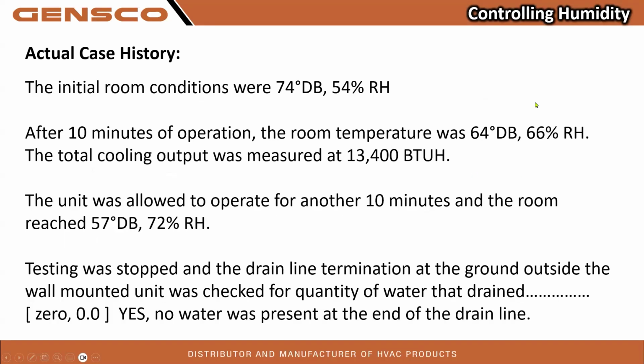The initial conditions were 74 degrees and 54% humidity. And after 10 minutes of operation, that room temperature was down to 64 degrees, 66% humidity. Humidity went up. And the total cooling output, this is not unusual, was double what it's rated to do. Ductless units overproduce. The unit was allowed to operate another 10 minutes and the room reached 57 degrees. That's a 17-degree drop in dry bulb temperature, and my humidity broke 70% in the room.